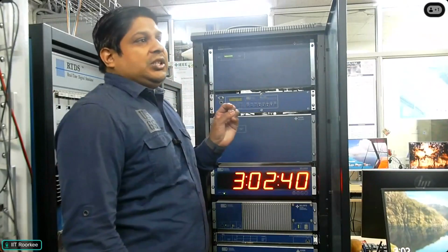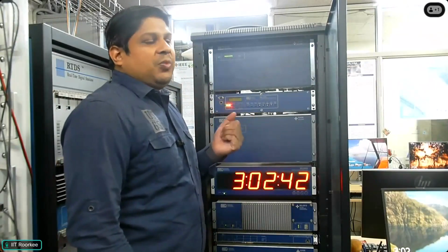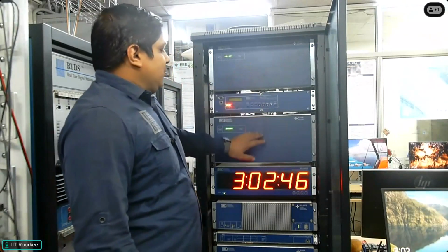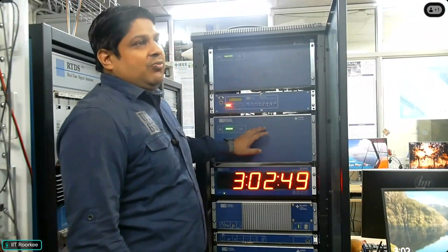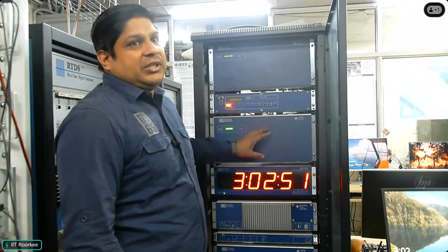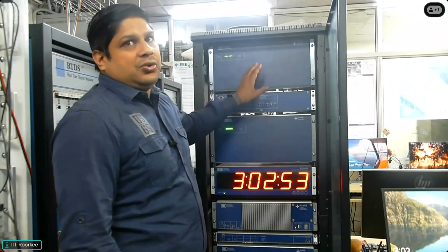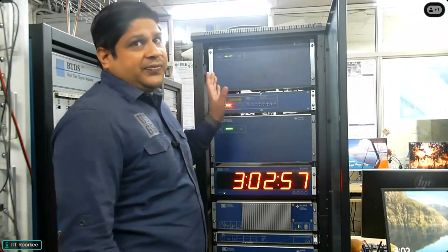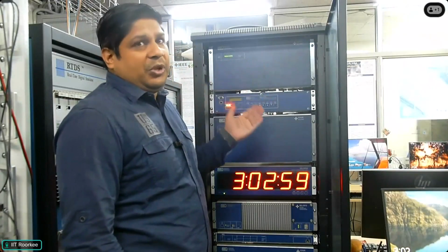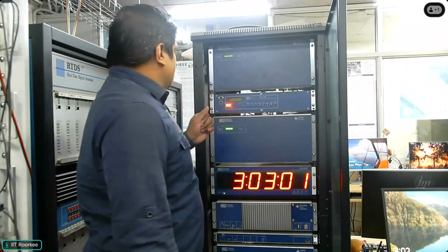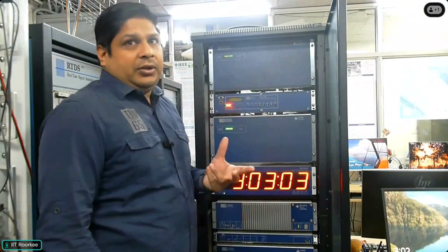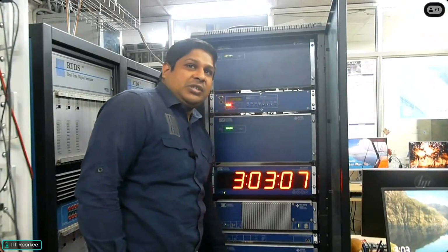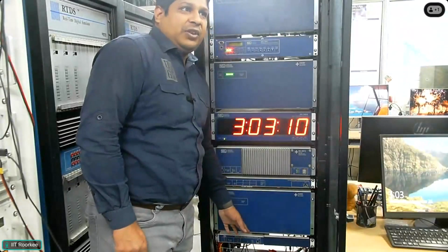But the signal coming out of the RTDS is maximum plus minus 10 volt. But these PMU devices require a minimum of 150 volt to sense the voltages and currents also. It cannot sense 5 volt or 5 ampere of current. So we need to amplify it. For that, we are using this CMC 356. It is from Omicron. So this amplifier we use.